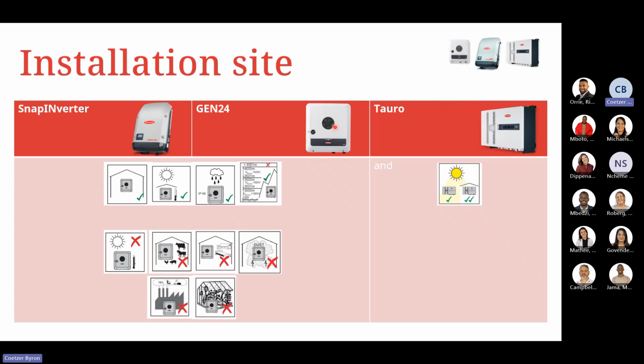As well as on the Gen24, the heatsink is directly on the front of the unit. So again, the unit can be installed outdoors. It's IP66 rated, and it can be installed at altitudes up to 4,000 meters. But we need to keep in mind our UDC max. So instead of being 1,000 volts, for example, it would shift down to 835 volts if we are installing at 4,000 meters above sea level.